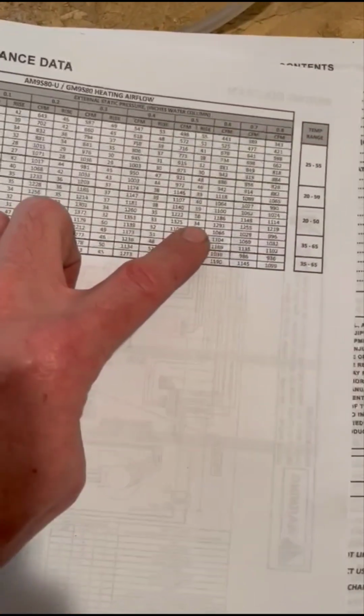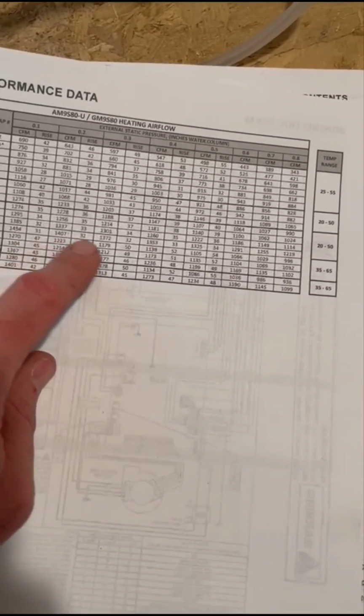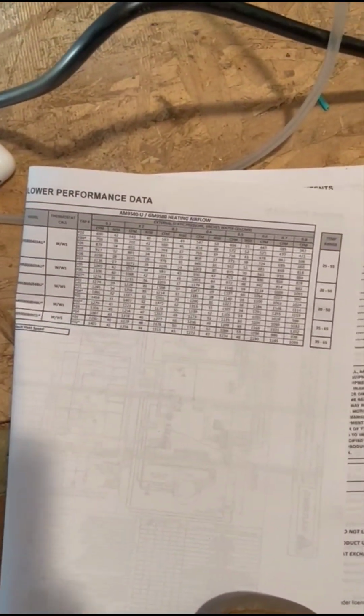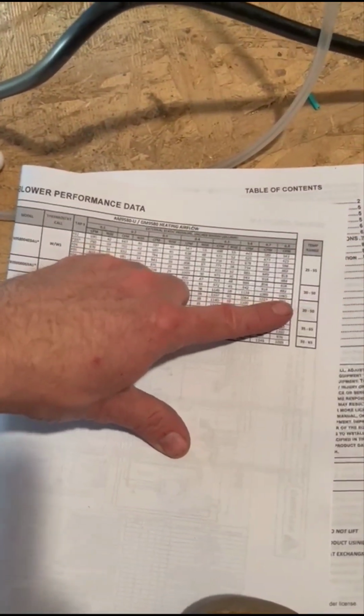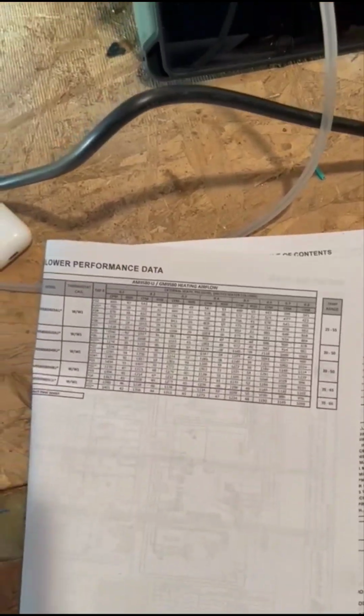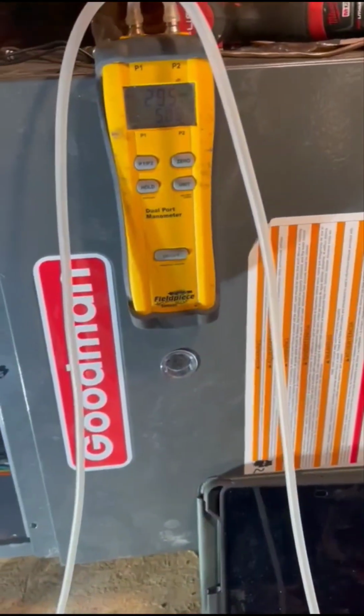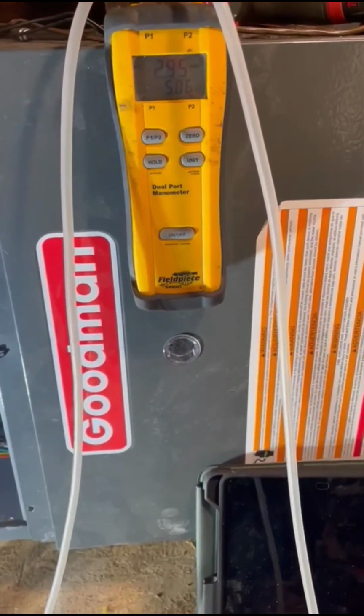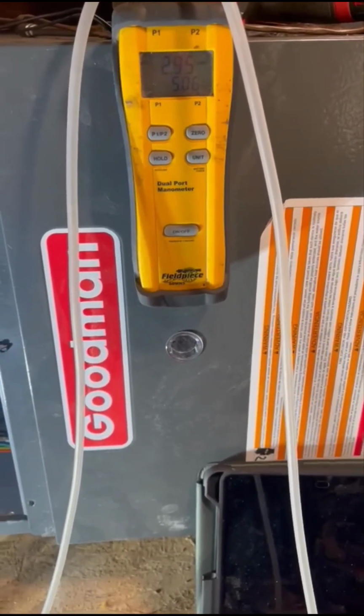Then we're running on tap 5, and our heat rise right now, I'm just looking at my JobLink probe. My iPad just turned off, but I'll send you a screenshot. That's 30-degree heat rise. So we're right within the range of 20 to 50 degree difference between the supply and the return. So commissioning is done. Just need to come in the summer to check the refrigerant charge, and that's it for today.